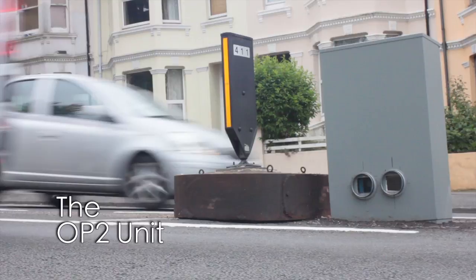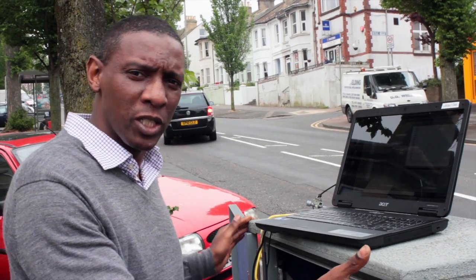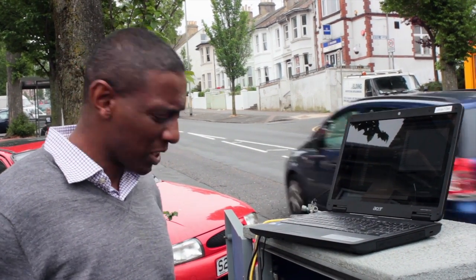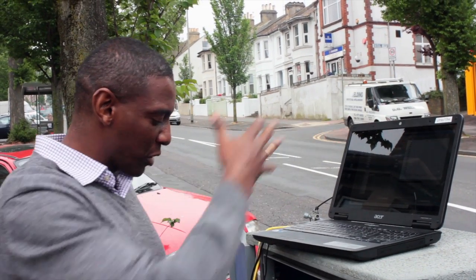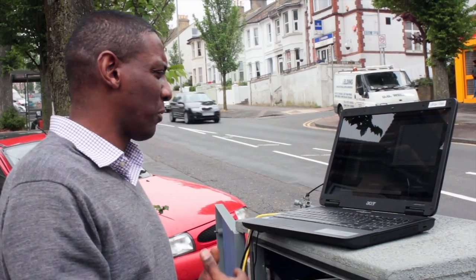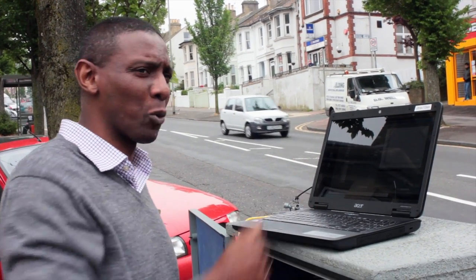Dr. Mark Richards is from Imperial College. He explains: 'This unit we refer to as the OP2 unit — the second generation of our open path unit. By open path, what that means is we send a beam of light across the street, it gets reflected and returns back to this unit.